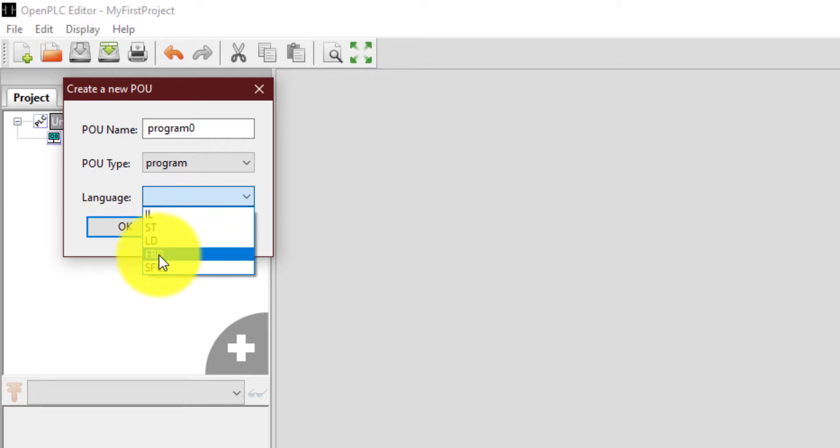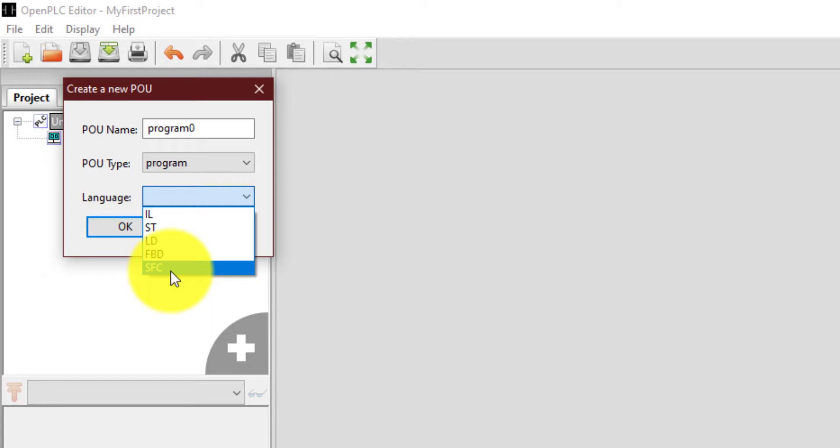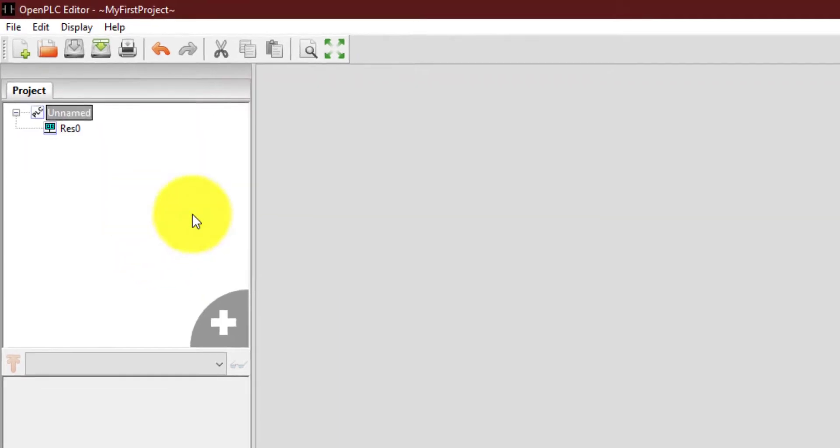And the very important thing is in which language you want to create this program. So if you drop down this thing, you can see that there are five options. The first one is for instruction list. The second one is for structured text. The third one is for ladder diagram. Fourth is the function block diagram. And the last one is sequential flowcharts. So no matter which language you want to program your PLC in, it is present over here. Right now I'm going to select ladder logic and click OK.